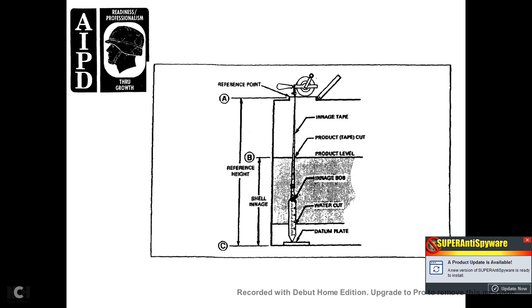This shows the innage tape going in at the reference point at the top of the lid. The diagram shows point A as the reference point at the top, point B as the product level, and point C as the bottom. Following the innage tape with the product tape cut, lower the bob and tape into the tank until the tip of the bob just touches the tank bottom or datum plate — at the horizontal plane of point C.